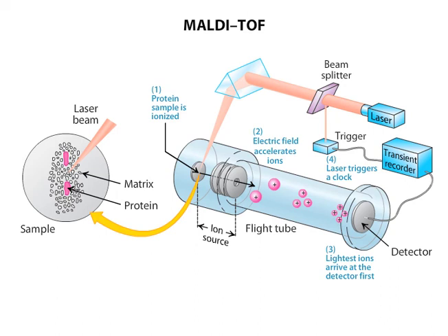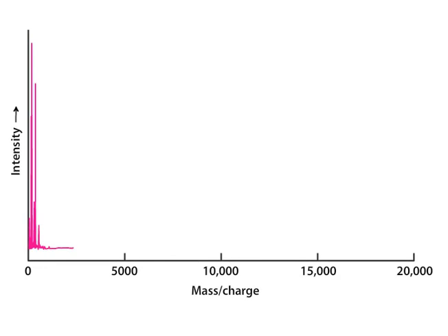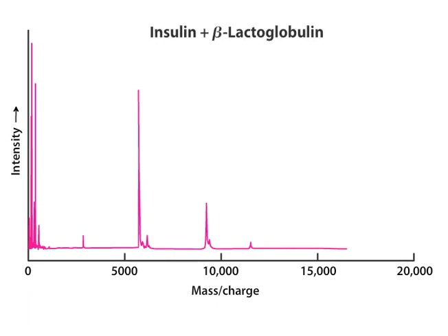The accuracy of MALDI-TOF can be experimentally validated by comparing the measured mass-to-charge ratio with the calculated mass-to-charge ratio for a sample of known proteins. For example, a mixture of the proteins insulin and beta-lactoglobulin produces a unique mass-spectrogram. In this mass-spectrogram, the peak at 5733.9 closely correlates with the calculated mass-to-charge value for insulin.